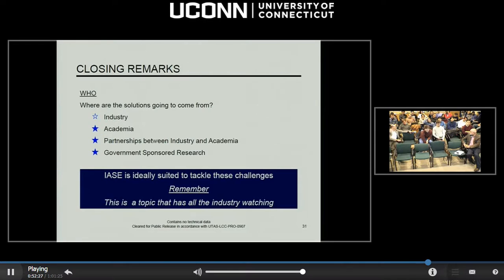Question: I really like the presentation, but what if something is wrong with your BITE itself? Do you have BITE to test BITE? That's why we only allow about 10% of the circuitry to be BITE — you have to prove the BITE is more reliable than what it's testing. The ambiguity group you get with that 10% of BITE is something you have to live with. You don't do BITE on BITE.